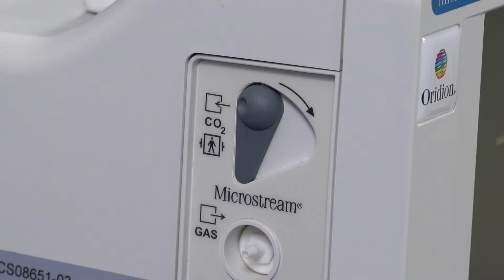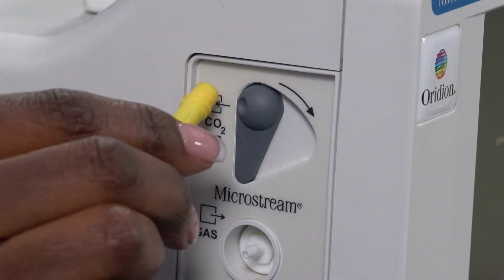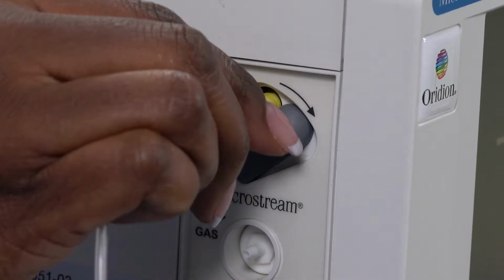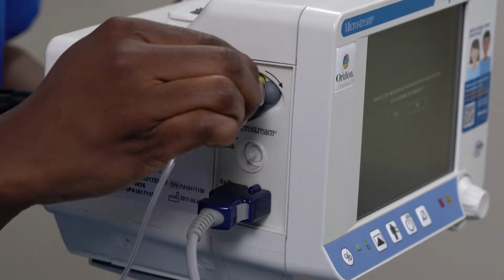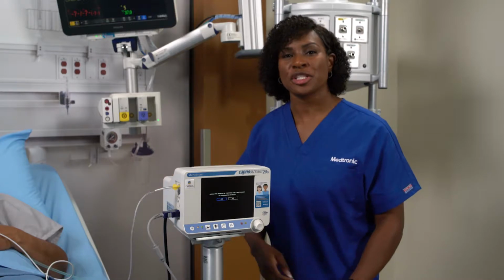On the side of the monitor, you'll see a CO2 input. Slide the gray trapdoor down and twist the quick seal connector a quarter of a turn. Once the sampling line is attached to the monitor, the pump will automatically engage.